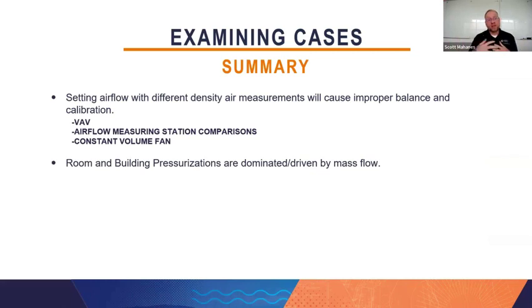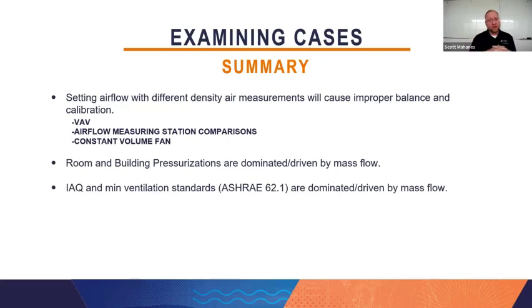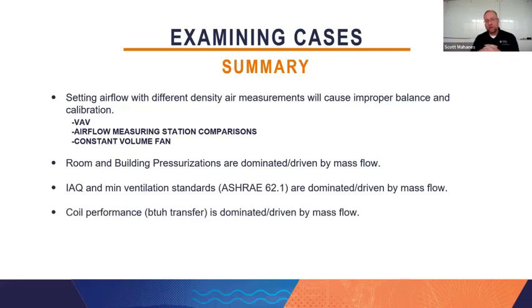Room and building pressurization is dominated by mass flow, not by volume. Indoor air quality or minimum ventilation standards, the ASHRAE 62.1 table of minimum ventilation rates, they are mass flow numbers. They are not volume. And so it's the mass flow number that is important to control to. Coil performance, we didn't talk about this, but coil performance or BTUH transfer is dominated by mass flow. It doesn't really care about volume. In fact, your 1.08 times CFM times delta T is kind of predicated on having a consistent standard density. If the density is different, the value is different.